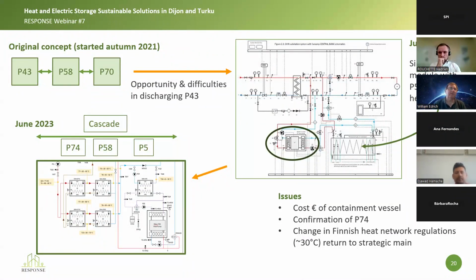So we came up with this solution where we put in a cascade of P74 and P58, and then added a P5 material, which changes phase at 5 degrees centigrade. We would use that material to help the return temperature go back to the strategic main at the plate heat exchanger at 30 degrees centigrade, by switching on a small chiller and reversible heat pump that helps balance the return flow back to the strategic main.